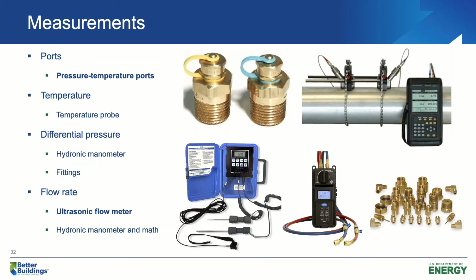So we just talked about some low-cost energy conservation measures and some capital-intensive technologies. For any of those measures and technologies, before you proceed to implement, you need to do some homework, some engineering analysis work, and some diagnosis. To do analysis and diagnosis, we need data on temperature, pressure, and flow rates. You can find temperature and pressure ports around your pumps and chillers. We call them PT ports. With those PT ports, or pressure temperature ports, you can use temperature probes and hydraulic manometers to measure the temperature and pressure. For flow rates, you can either use ultrasonic flow meters, or you can use the relationship between pressure drops and flow rate to derive flow rates for you.